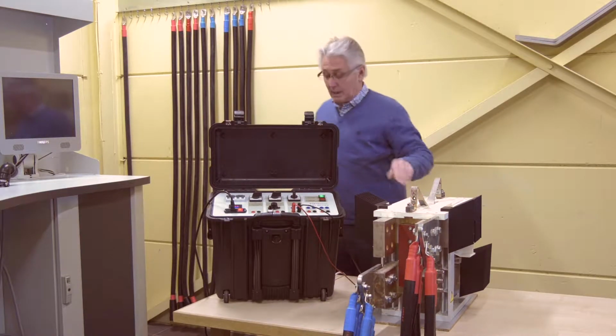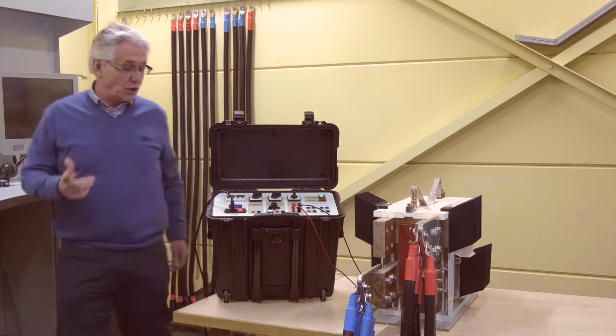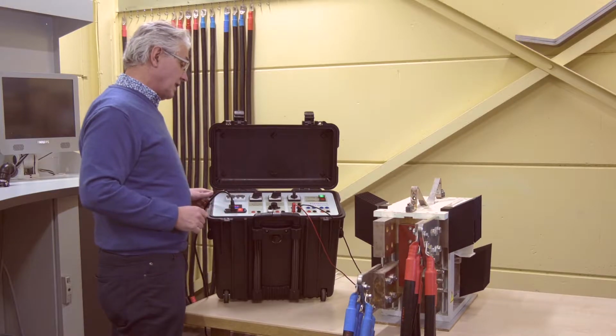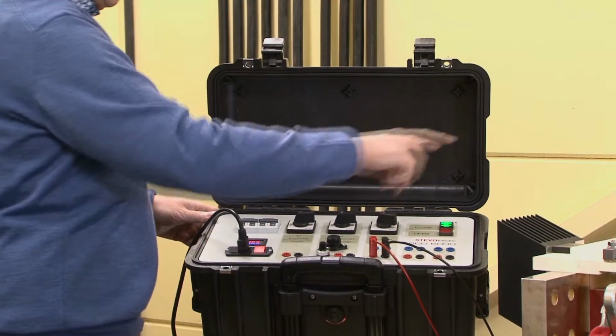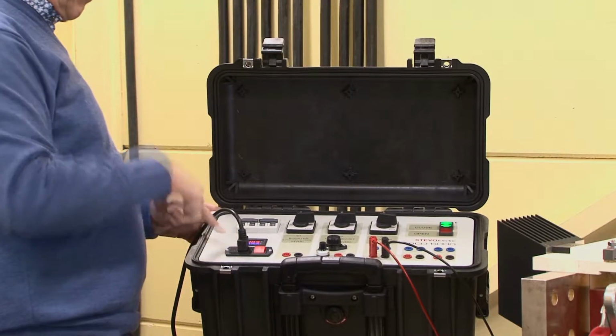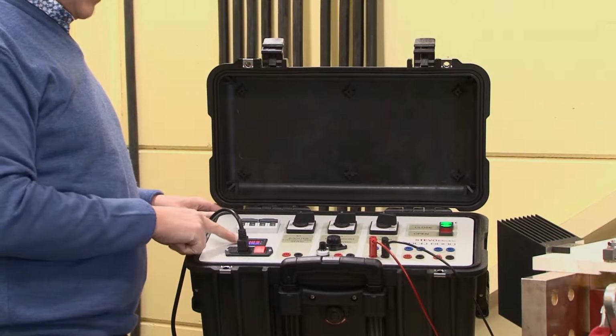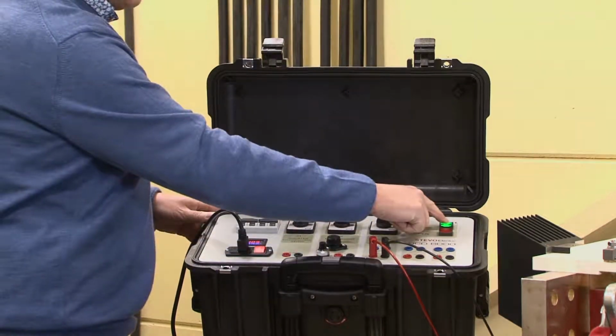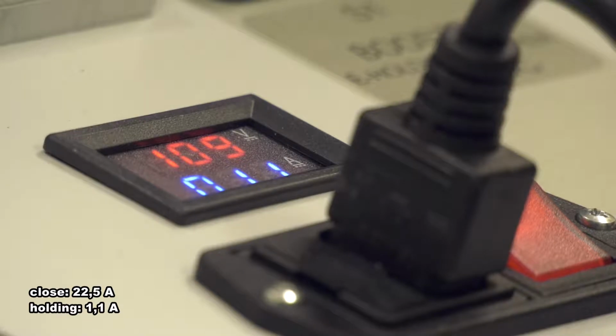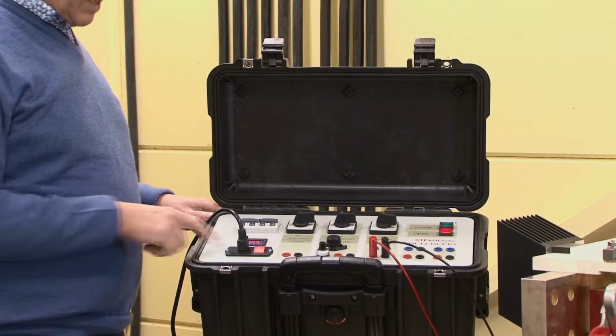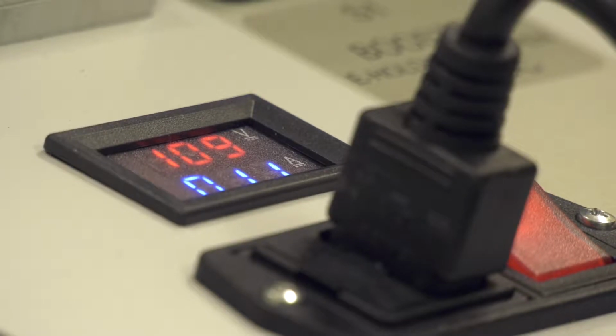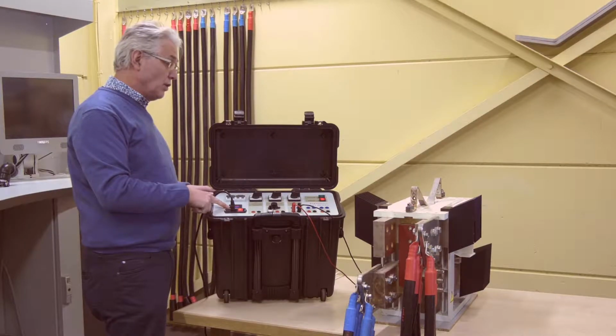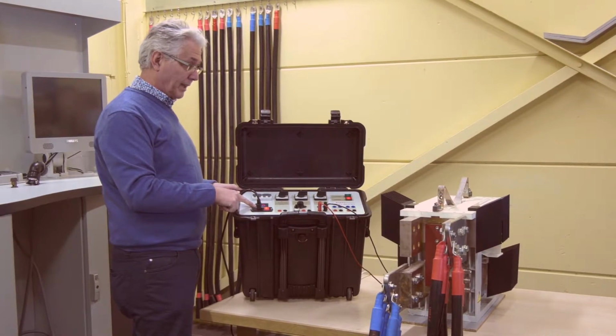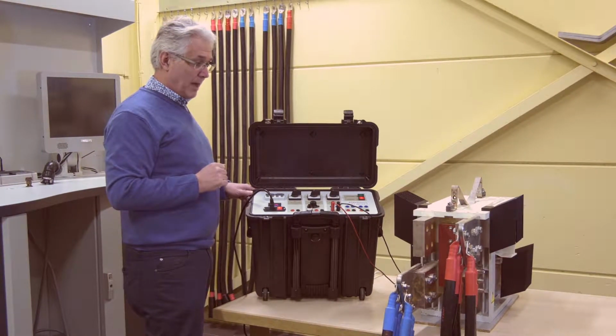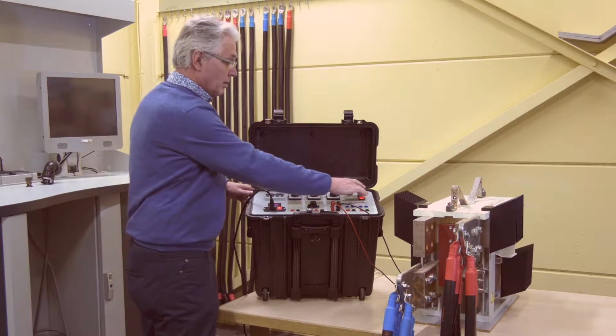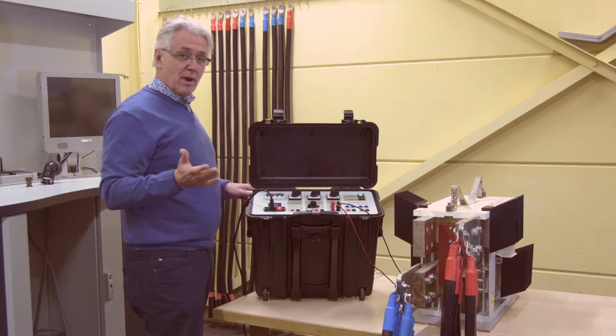This circuit breaker works with electrical holding, so we should make sure that the switch is set to electrical holding. Check the voltage. Okay, we got 109 volts here, which is in line with the 110 volts requested. And let's close the breaker. Alright, the breaker is now closed, and you can see here on the display that a current of 1.1 amps is used to generate the electric holding current. Opening the breaker is exactly the same, and the breaker is opened.